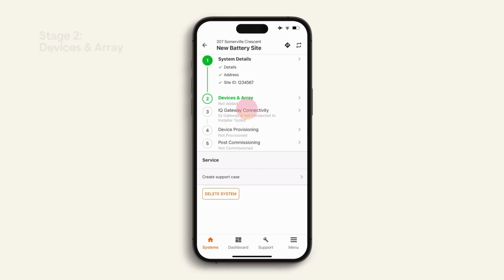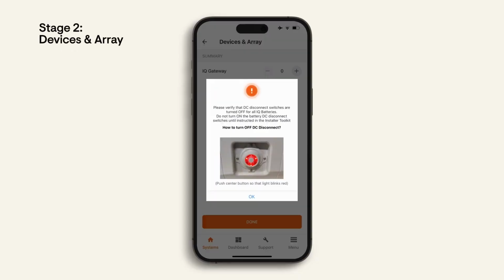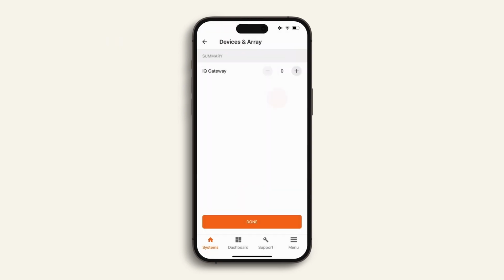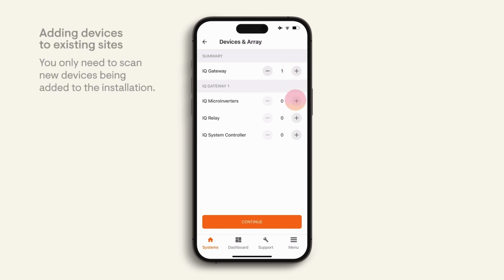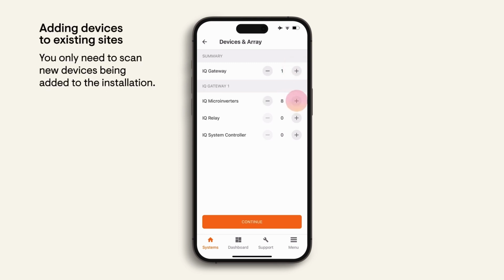Now I'm going to show you how to program device serial numbers when you commission an Enphase energy system, including a simple method for quick scanning of the devices. But before you start the task, ensure that the DC switch on the front of the battery is turned off. The LED should now show red. Begin by adding the number of devices to be installed on site. An existing site will already include the number of microinverters. You will only need to scan for new devices installed.